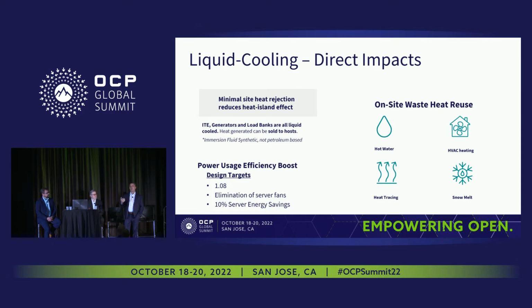But we're also doing all the obvious stuff. We're in Wyoming, so it gets a little cold during the winter. Winter dry bulb design temperature is somewhere in the ballpark of around minus 30 Celsius. So guess what, we've got HVAC heating for the building proper. We're using data center heat recovery to heat the data center. We're also using it for snow melt, and for heat tracing all of our outdoor or underground lines that are at potential risk.